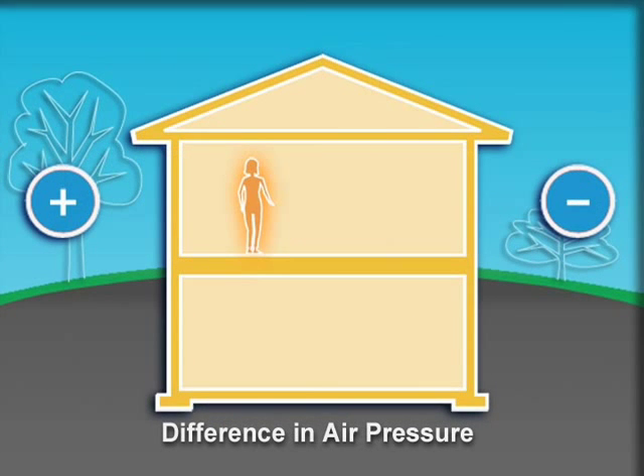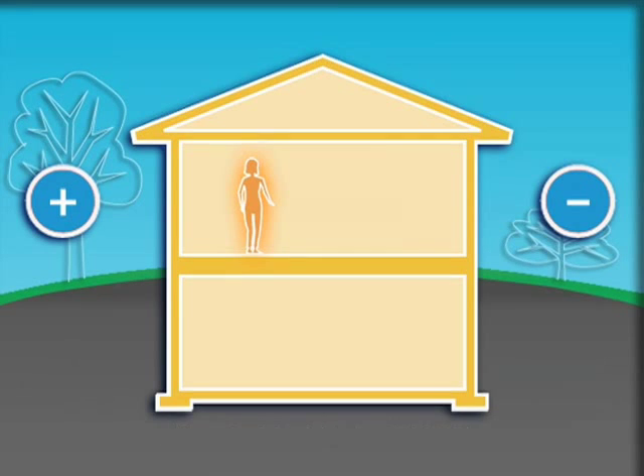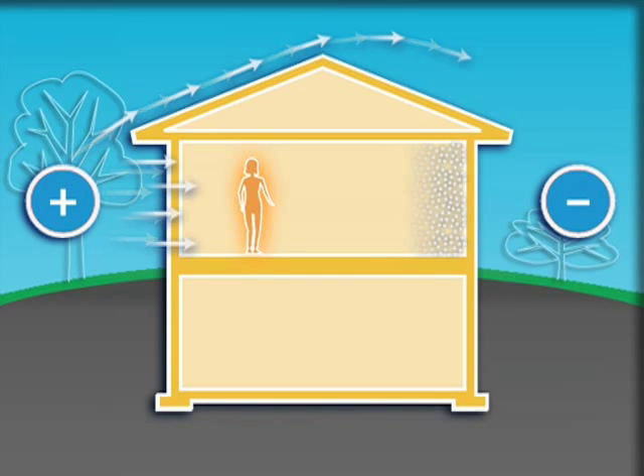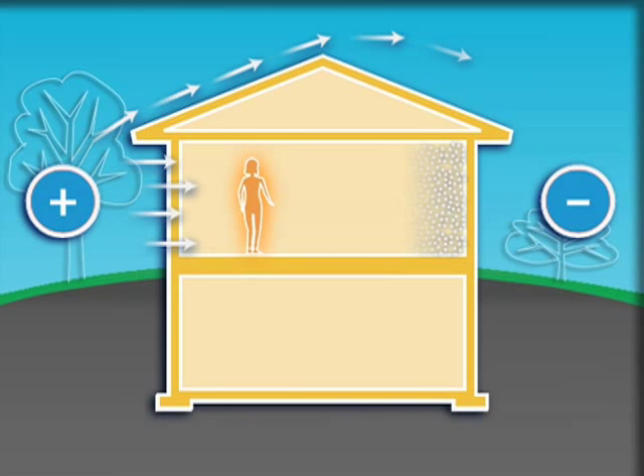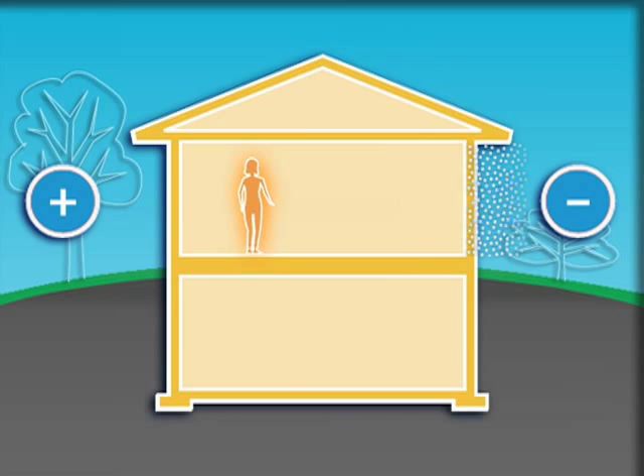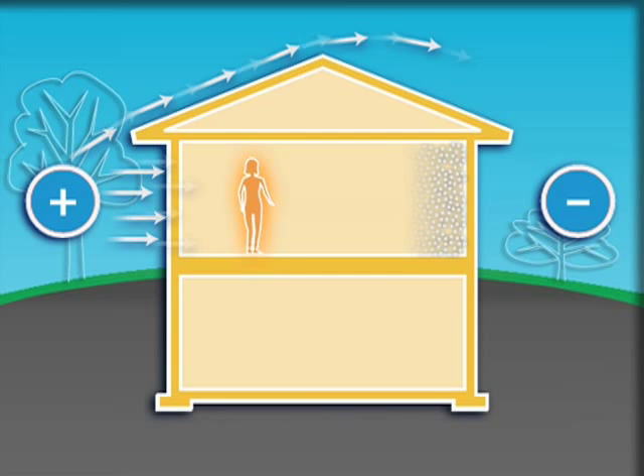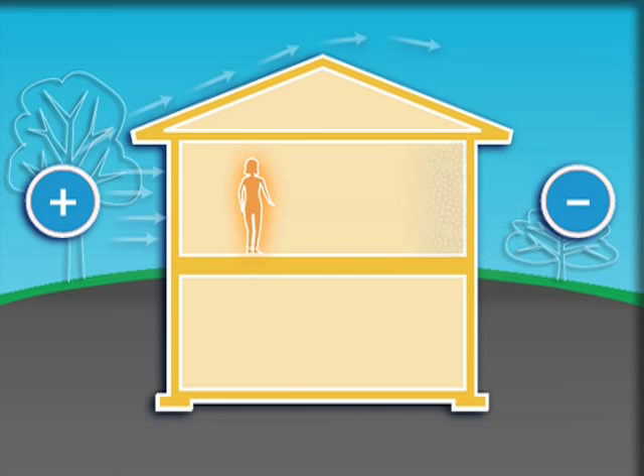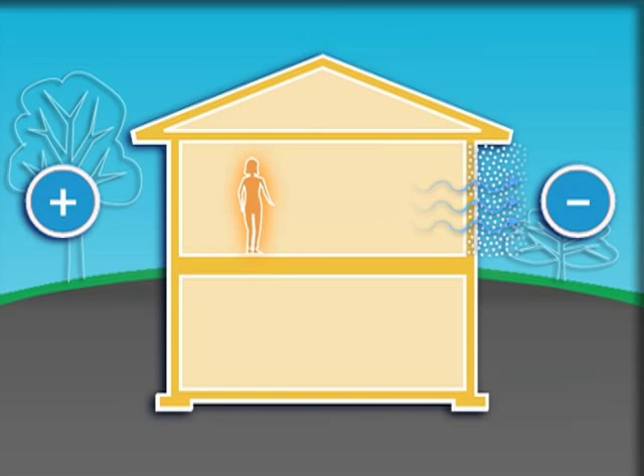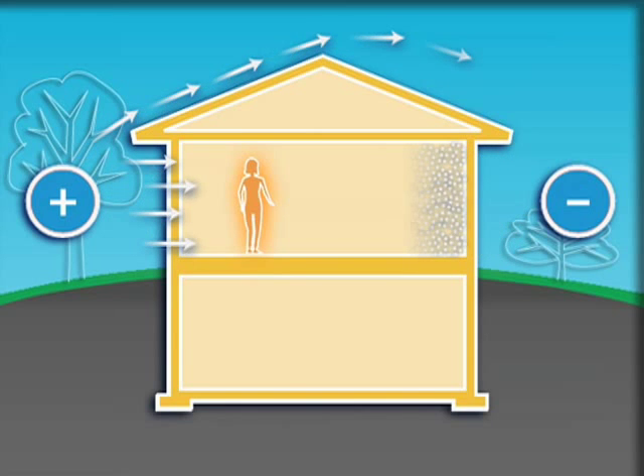A difference in air pressure is another force that allows air, water vapor, and energy to flow. A difference in air pressure can be created by the wind. When the wind blows against the house, it creates a pressure difference across the building. On the windward side of the home, air flows in. On the leeward side, air is drawn out. This airflow can carry energy and moisture into the home and out of the home.